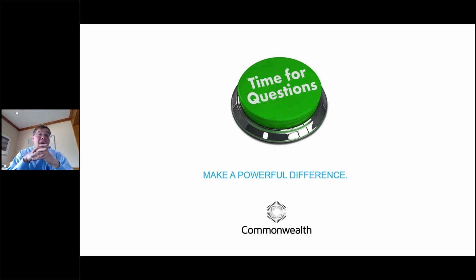Now, all of that really shouldn't require a terrifically huge study, and it ties into the grounding issue. One of the things that we do with grounding is a lightning impact study. But normally, if you can show that your plant is effectively grounded, that might take care of it without doing an in-depth study. But yes, that's certainly going to be an issue in some places. For example, in Florida, I would think it would be a big deal, as opposed to California and some other places with fewer incidents of lightning.